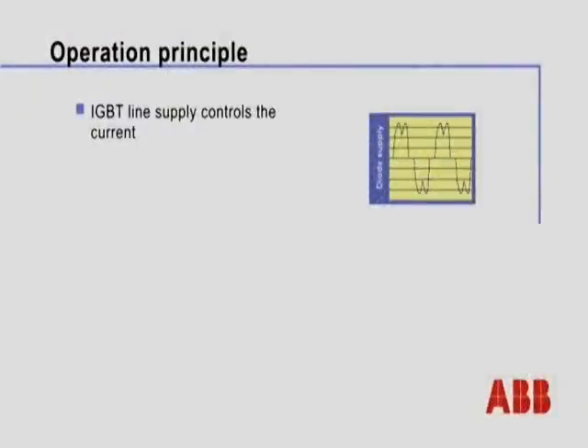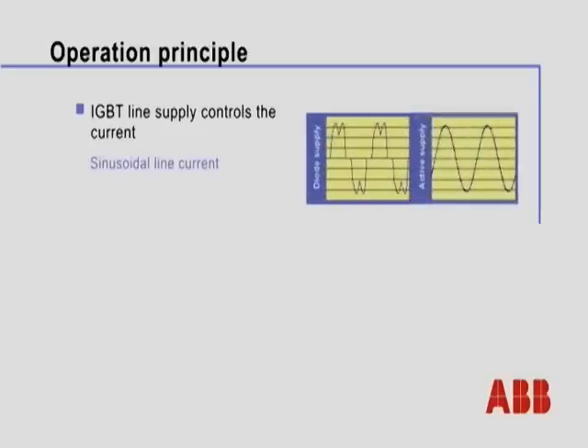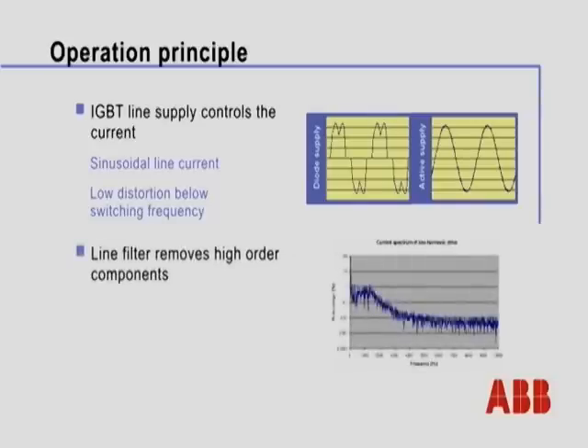The operating principle of the active supply or active input is essentially the same as the inverter section of an AC drive. Just as the inverter section takes the DC bus and creates a near sinusoidal current waveform out to the motor, the active front end provides a near sinusoidal current waveform to the AC line. The only noise that we see, in fact, is the switching frequency or carrier frequency noise, which is why we utilize in the ACS800 an LCL filter. This LCL filter strips out and cleans up that switching frequency noise, providing near pure sinusoidal waveform in terms of current to the AC line.